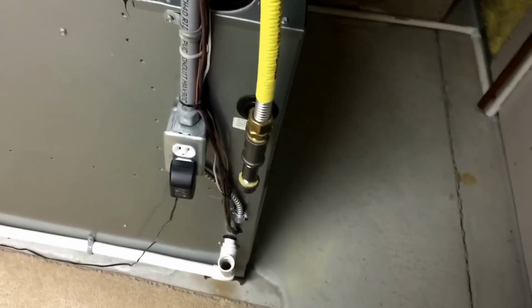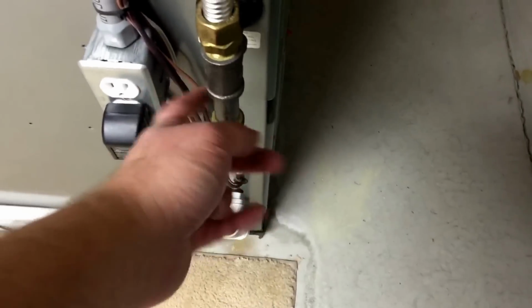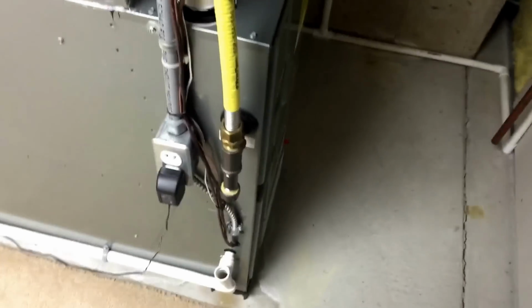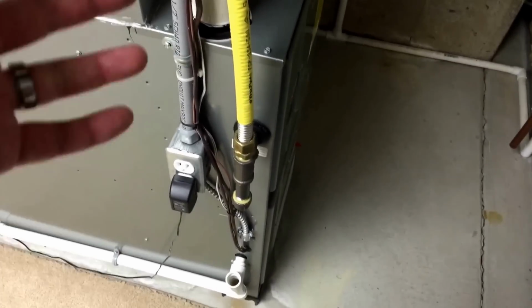On the natural gas line, there's a drip leg. I see so many furnaces and hot water tanks installed with no drip leg. Notice the shutoff valve is up here where kids can't touch it, since this is a basement. You can shut it off, and if you have to do work on this furnace, like remove a gas valve, the shutoff is there, and there's a union right here so you can disconnect it and actually work on the piece of equipment.